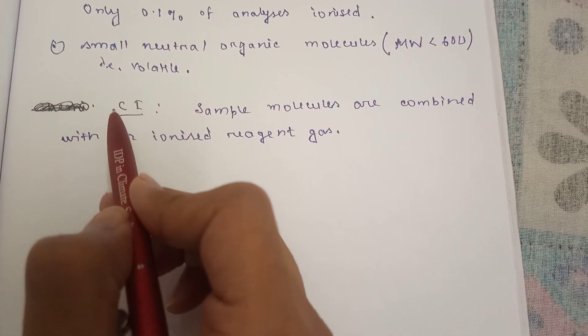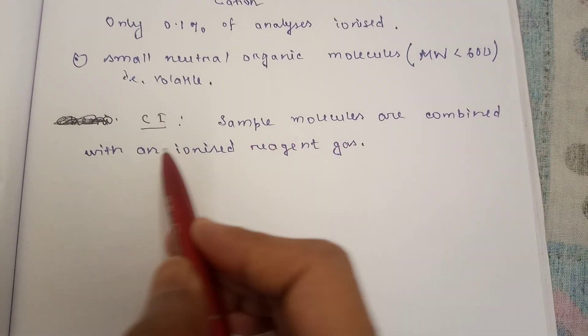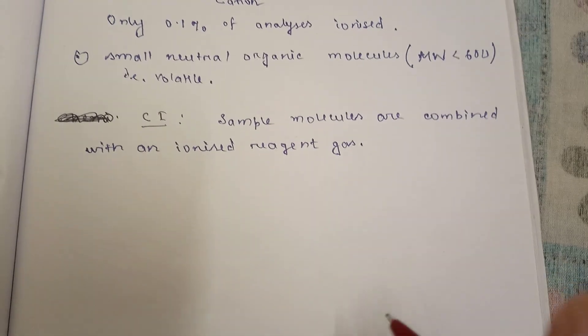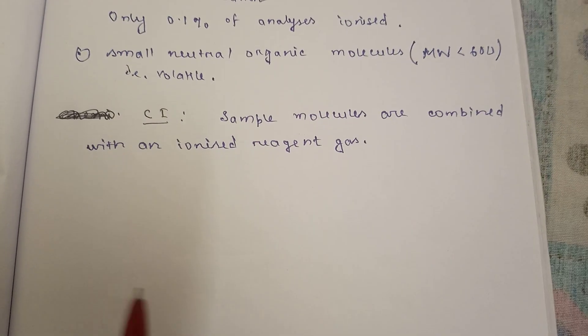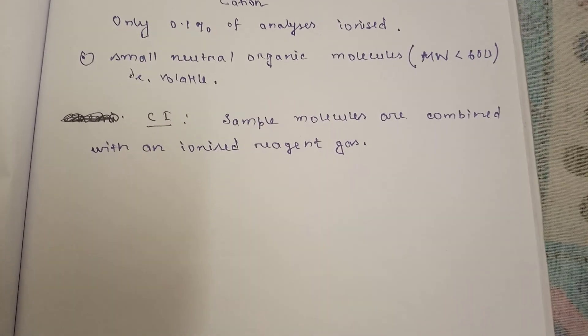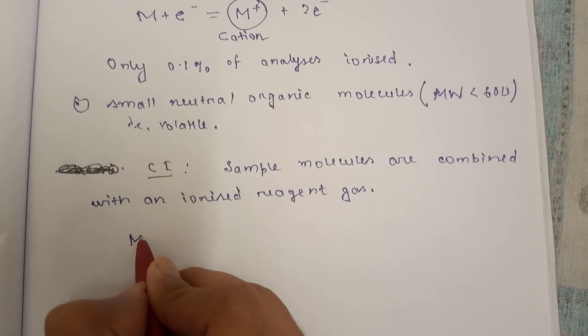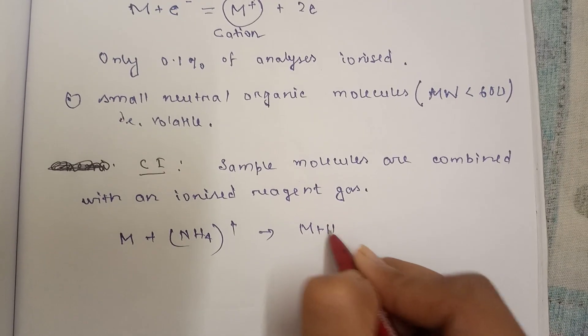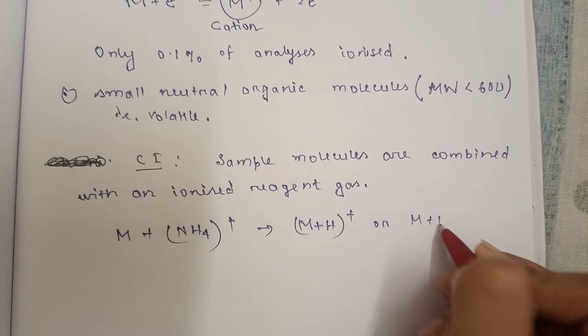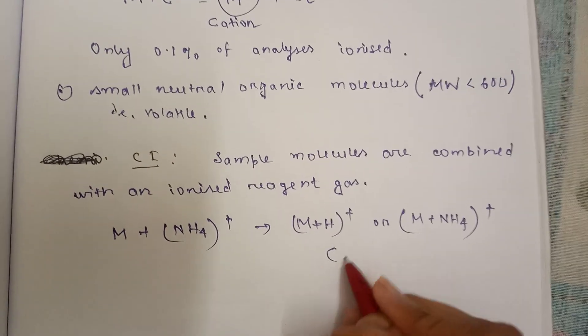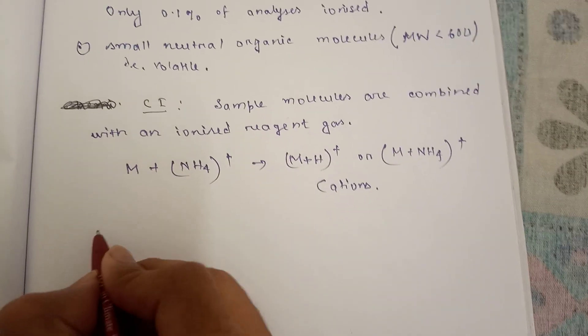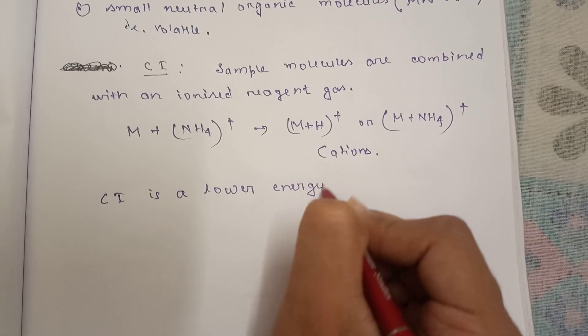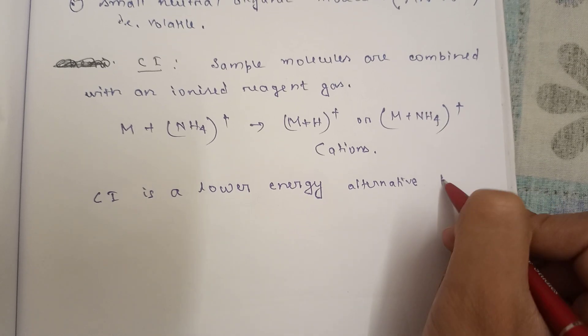The second method is chemical ionization. The sample molecules are combined with an ionized reagent gas. When the sample molecules collide with the ionized reagent gas, some of the sample molecules are ionized. There can be various mechanisms like proton transfer, electron transfer, or adduct formation. If M is the sample and it's hit by NH4 plus, it can create M plus H plus or M plus NH4 plus. These are cations. CI is a lower energy alternative to EI.